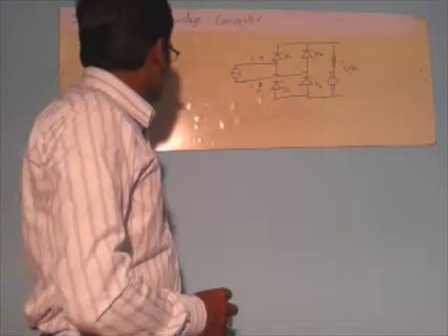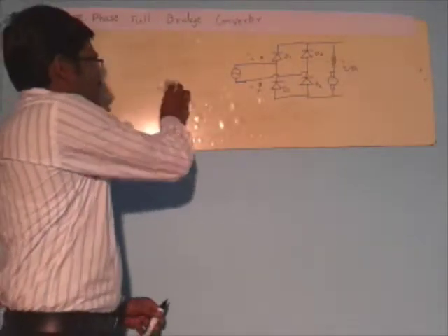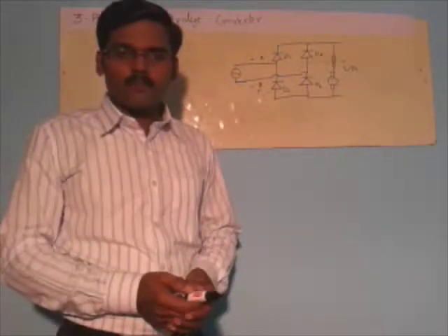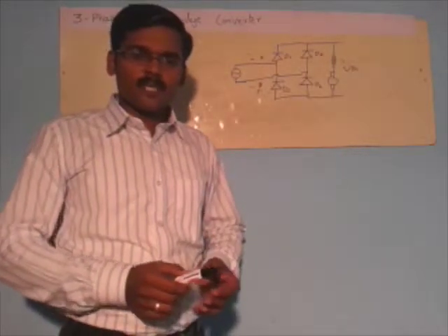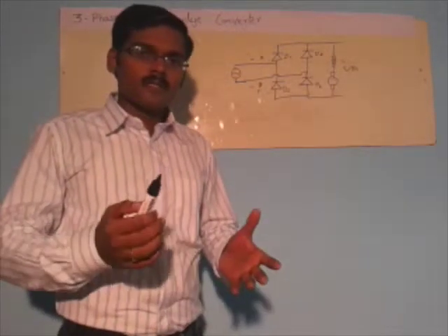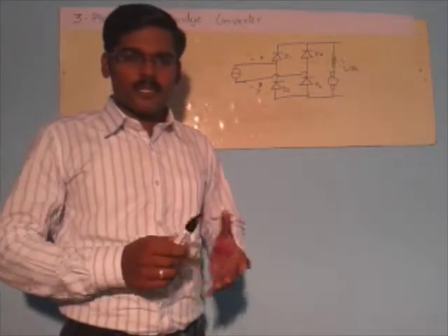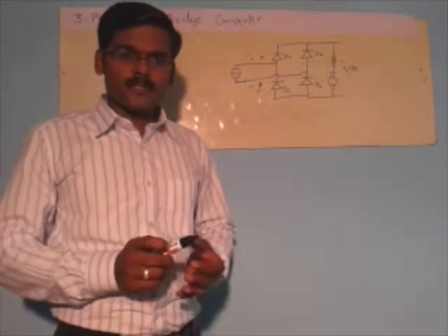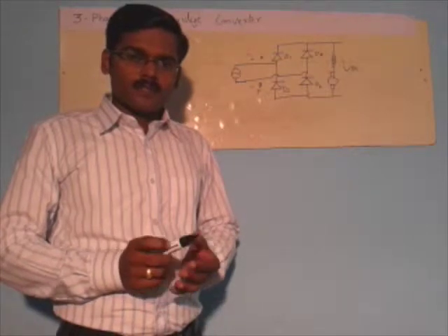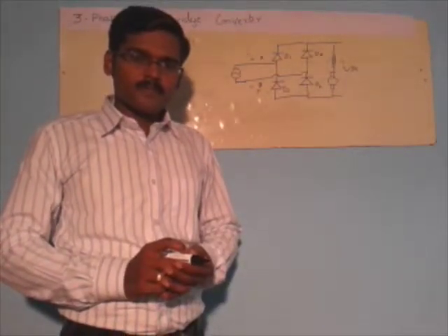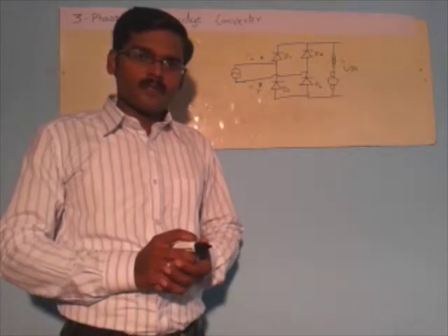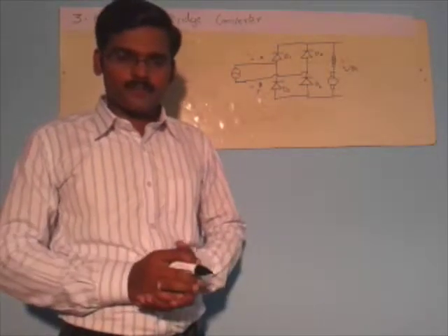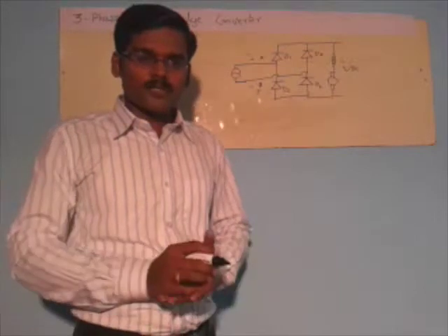Next, we discuss harmonic profile. Harmonic profile is another important performance characteristic, especially THD, total harmonic distortion. What is THD? THD of a source current is defined as the ratio of harmonic content to the RMS fundamental current, that is total harmonic distortion.